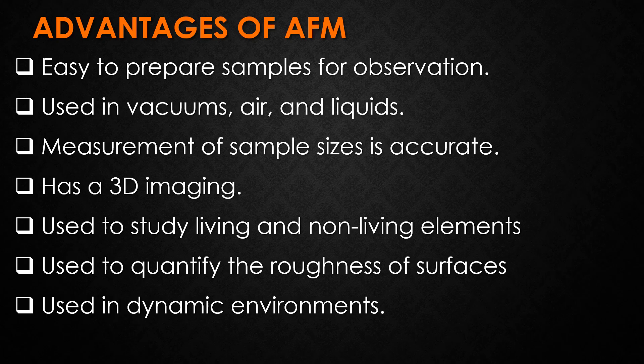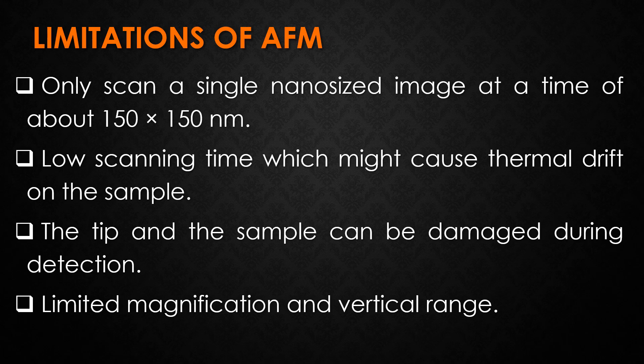Some of the limitations of atomic force microscopy include: AFM can only scan a single nano-sized image at a time of about 150 by 150 nanometers, and AFM has a low scanning speed which might cause thermal drift of the various samples. The tip and the sample can be damaged during detection, and finally AFM has limited magnification and vertical range.